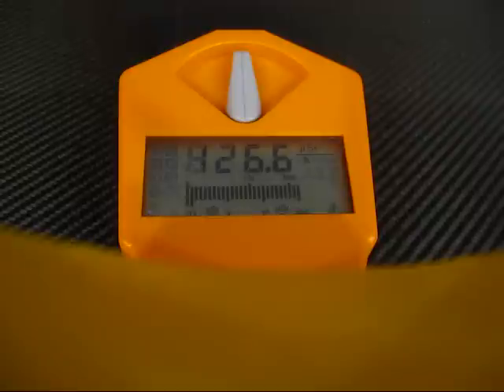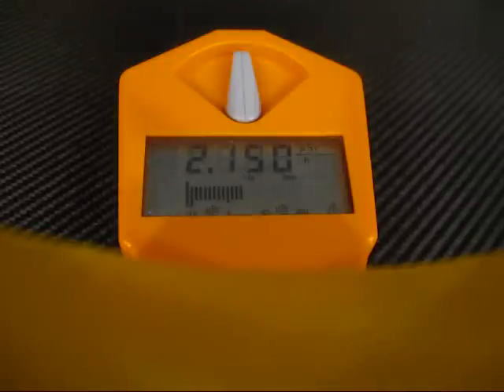But what about the neutrons? Now we see the dose dropping as the machine, the LINAC, is switched off. And you can see the dose rate on the Gamma Scout doesn't drop to normal levels. It's usually 0.2 microSieverts per hour as it was before, and now it's over 2 microSieverts per hour. What the hell is happening here?